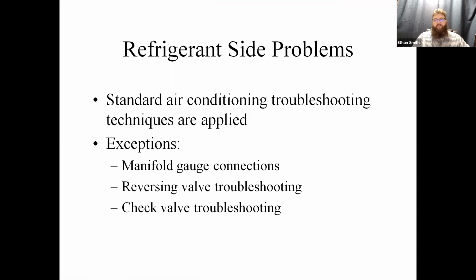Refrigerant side problems with heat pumps. Standard air conditioning troubleshooting is going to apply, guys. Just be aware that if you're in the heating mode, you've got a metering device in the outdoor unit now. It's going to operate the same way as your metering device on an air conditioner, with that same superheat target. You're going to expect slightly different subcoolings typically, but not dramatically different. A couple of exceptions, guys: you've got to be aware of where you're gauging up, especially in heating mode. Make sure that you're getting a true suction reading.